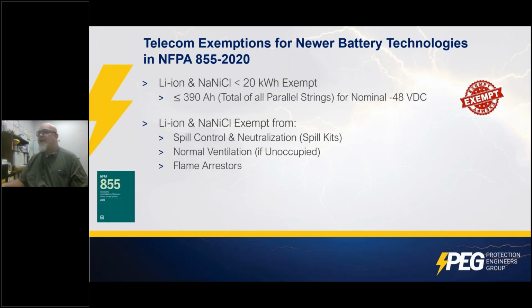Lithium ion and sodium nickel chloride, less than 20 kilowatt hours were exempt. So smaller, it was considered these newer technologies were not, how should I put it, were not as safe yet or proven to be safe. So they've started being regulated at a smaller value, 20 kilowatt hours, much smaller than 70 kilowatt hours. And they were exempt from spill control because neither of those battery technologies can spill. And normal ventilation, although they do have some significant requirements for emergency ventilation, especially the lithium ion. But normal ventilation, they don't release gases. And then they're exempt from flame arresters too, because they don't release gases. They're a sealed battery under normal conditions. Next slide.